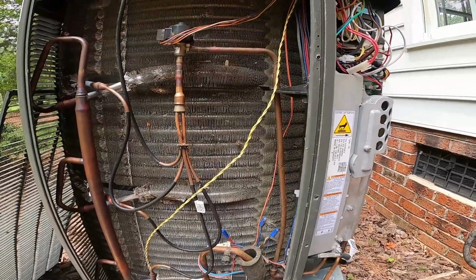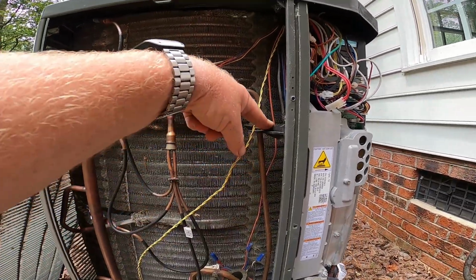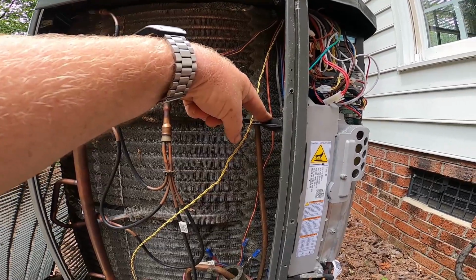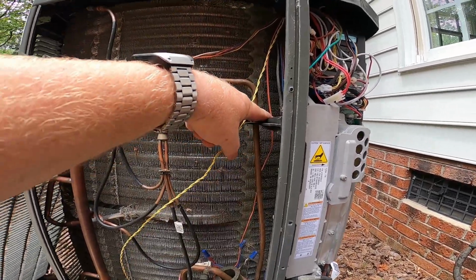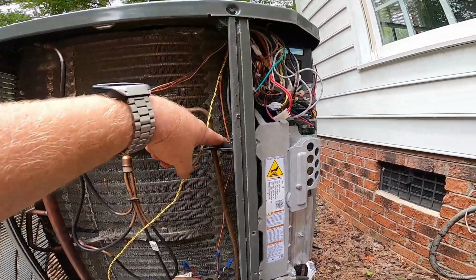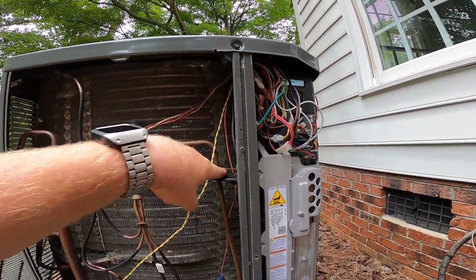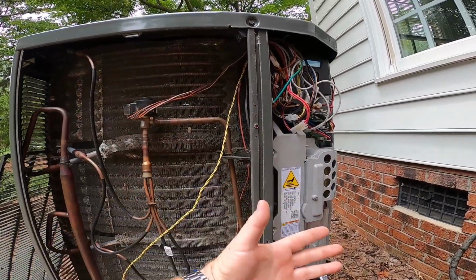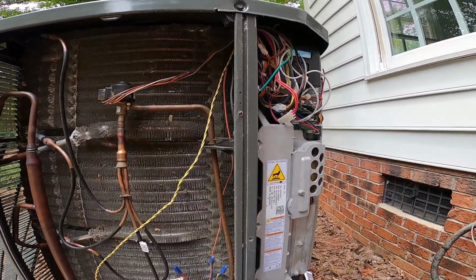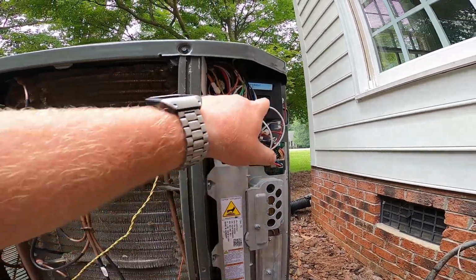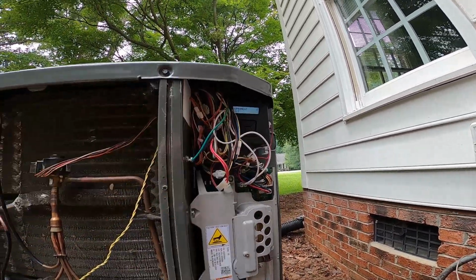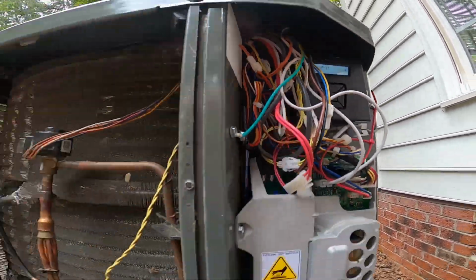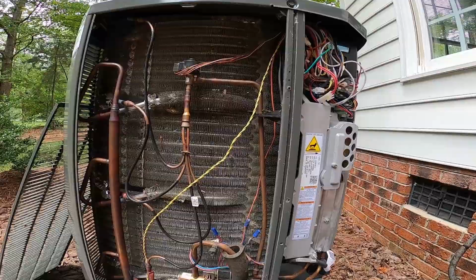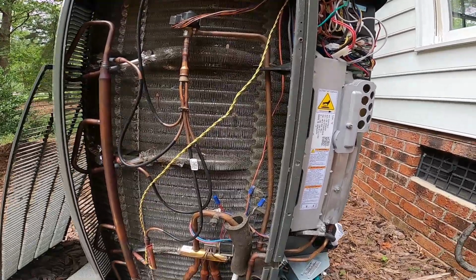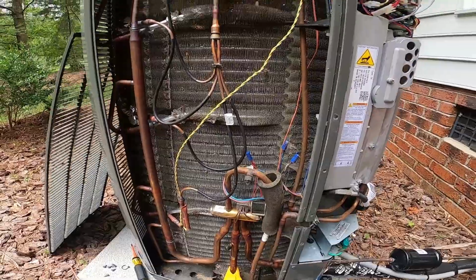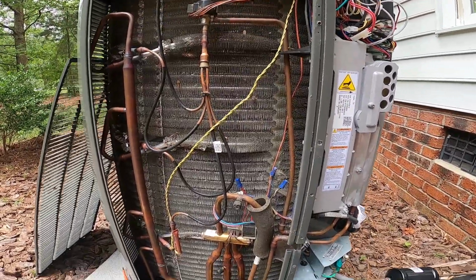The new model now comes with a liquid line transducer on it and a liquid line temperature sensor. The new models of these XV units this year will give you superheat and subcooling, high and low pressure, whether you log into the app on the new equipment to see your gauges and your pressures, or you can go into the drive CDA up there and get your pressures and your superheat and subcooling. So you can hook up to these new models without having to use gauges unless you have a refrigerant problem and you think you need to hook up with your gauges. But as far as just doing a maintenance or a quick check, there's no reason to pull out any gauges.